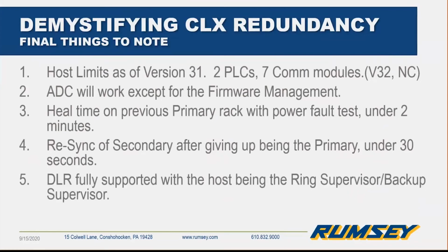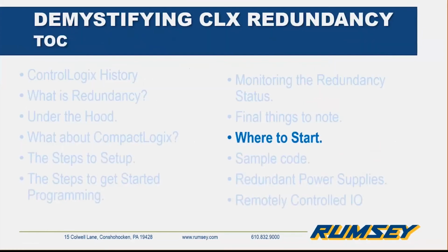DLR is fully supported. Can't stress enough. You can set this up. It's really nice to have your supervisor and your backup supervisor as the primary and secondary Ethernet modules in your primary racks, host racks.